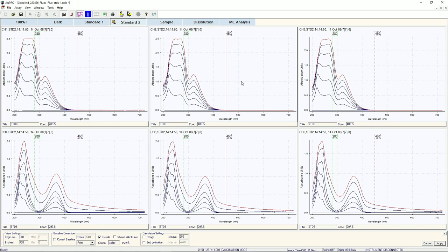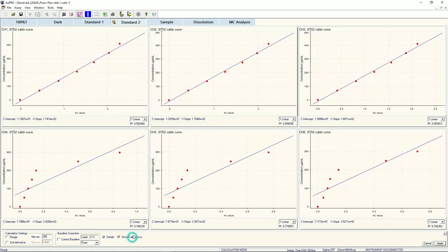The default settings, with no baseline correction and quantitation from only the absorption response at 280 nanometers, give standard curves looking like these. The value of R squared produced for the felodipine curves is clearly unacceptable. It seems the last concentration points have precipitated. To process these standards, we will apply the standard quality check function in the automatic data processing options.